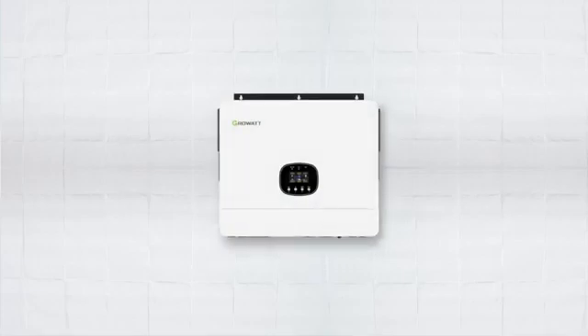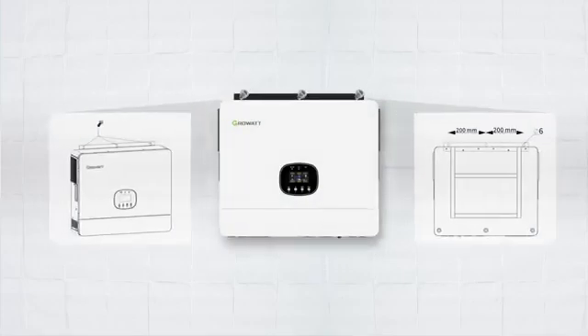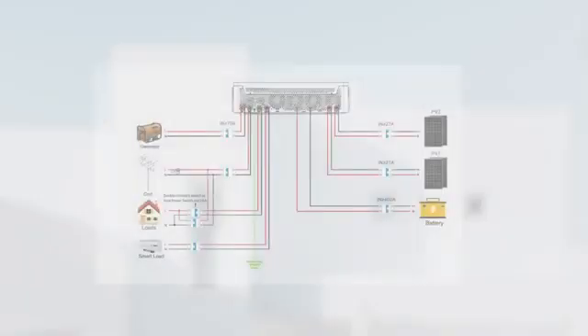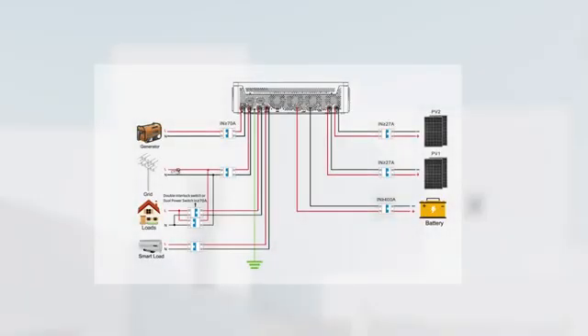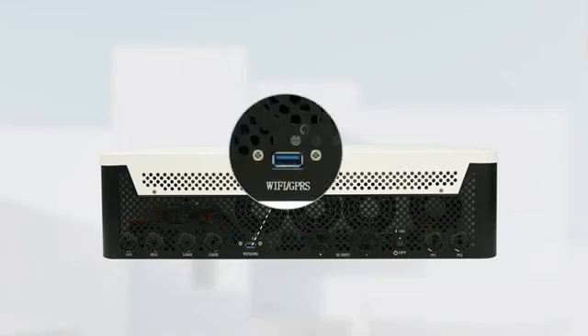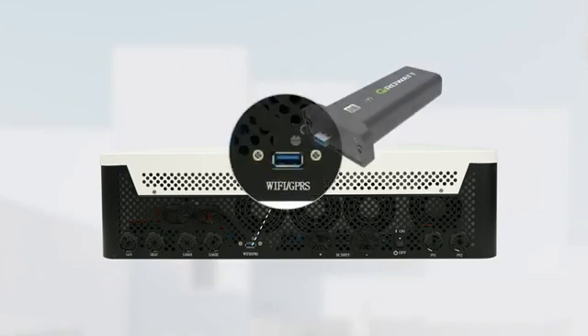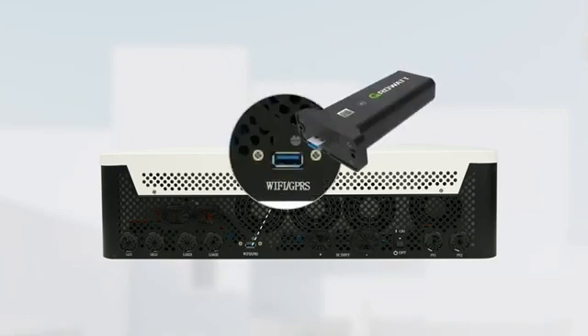Install the unit using three screws; it's recommended to use M4 or M5 screws. After that, connect PV, AC input, and output wires to the inverter ports. For the communication port, plug Wi-Fi or 4G loggers into the corresponding port and tighten with screws.